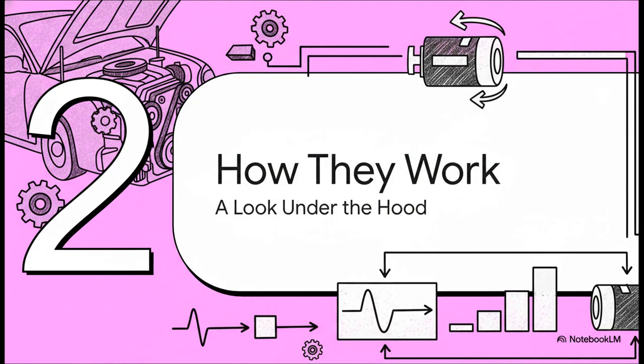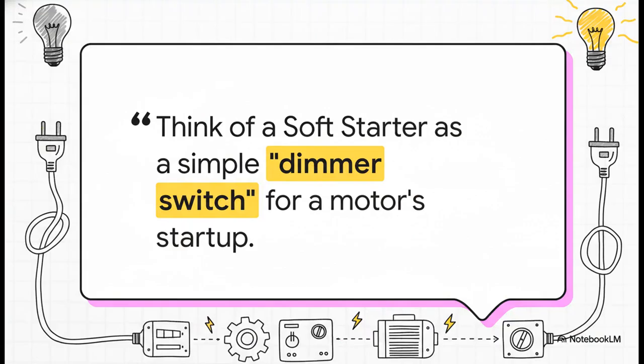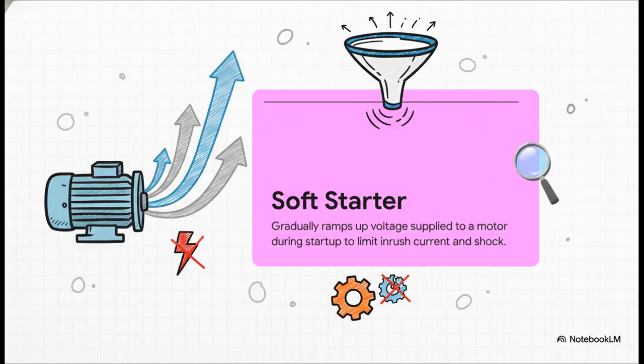Let's pop the hood and take a look at the fundamentals behind each one, because their approaches couldn't be more different. The absolute best way to think about a soft starter is with this analogy right here. It's basically a giant dimmer switch. You know how when you turn on a light with a dimmer, you can bring the brightness up nice and slow and smooth? A soft starter does that exact same thing, but it's doing it with electrical voltage for a huge motor. So here's the more official definition. It's a device that smoothly, gradually increases the voltage going to the motor, but, and this is important, only during startup. Its entire job is to manage that initial power up.